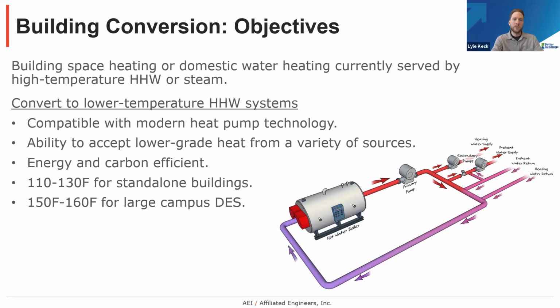A main one of going to lower temperature systems is compatibility with modern heat pump technology, and the ability to accept lower grade heat, whether it's a heat source or a heat sink from a variety of sources in the building or in the local environment. This compatibility and wide range of operation is really important, especially at smaller pieces of equipment or the smaller commercial building scale. It's also more energy and carbon efficient as compared to fossil fuel combustion or electric resistance. When we talk about lower temperature heating hot water today, I'm really talking about the range of 110 to 130 degrees for standalone buildings. If we're talking at a larger scale, whether it's a campus district energy system or more of the industrial scale, we can get closer to 150 or 160 degrees F, which is the common temperature for those. So when we're talking about converting to lower temperature hot water, those are the ranges we're talking about here.